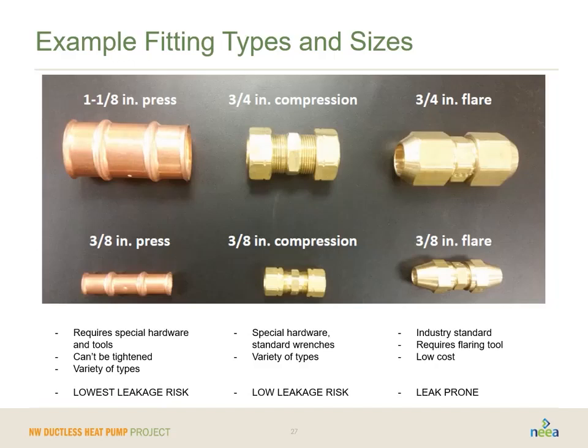There are a variety of different fitting types in the market. Some of them are used for creating flares, and that's going to be pretty common, particularly as you connect to the outdoor unit and the indoor unit. But what about if you ever need to do additional connections? Here are some examples of fittings that aren't full flares: the press fitting and the compression fitting. These are specialty equipment that you usually have to get separately. But what we find is these have lower leakage risks than a standard flare. A standard flare fitting really does take a lot of experience and a little bit of luck and proper application of oil and proper torque to get these really well. Whereas the compression and the press fittings are a little bit more simple and easier to master. Again, you do have to purchase them separately, but they can really elevate your game in terms of reducing the chances of having refrigerant leakage.